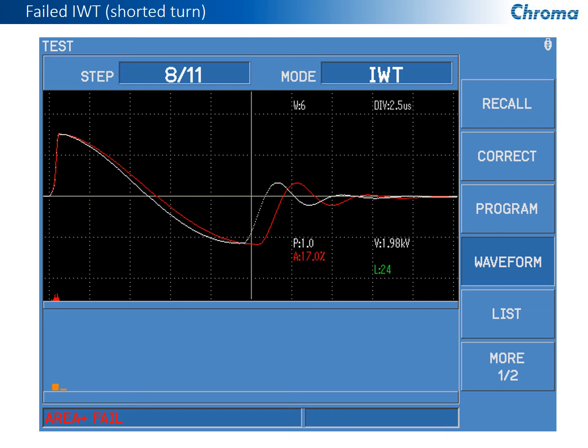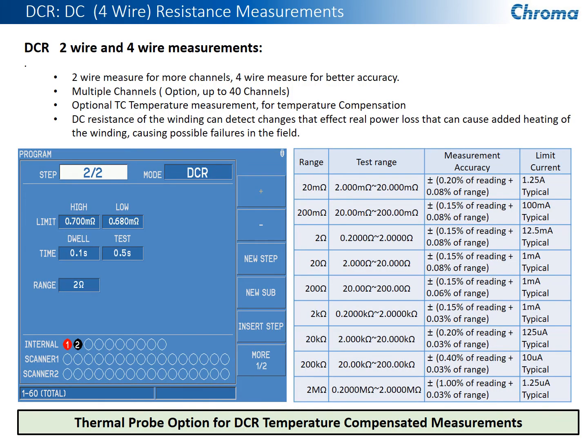The red, again, is the device under test waveform. The white would be the sample waveform. So you can see the various differences in the area and the shape of the waveform, and that's used, like we said, to detect if there was some type of a breakdown or difference in the 2 windings. Slide is that we also include a thermocouple temperature probe option for this unit, which allows you to, in low resistance measurements, include temperature compensation to get the best accurate measurement for your resistance of your winding.